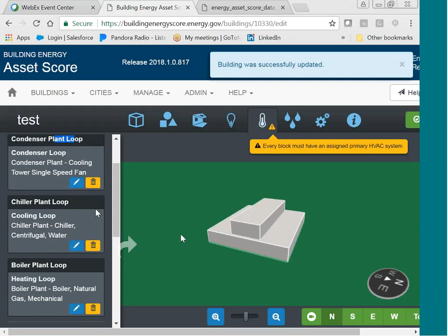So remember the loops — the loops are not assigned to a block, these are assigned to the whole building, and you can't drag and drop these. But you want to know, does the chiller plant loop serve... excuse me, you've got a condenser loop, a chiller loop, a boiler loop. They're building-wide. But the distribution equipment, like air handlers, can be assigned to a block.